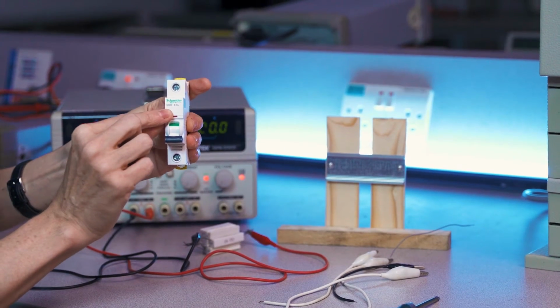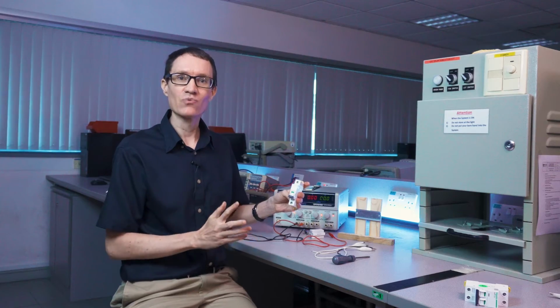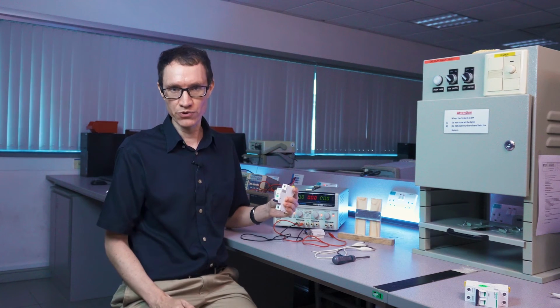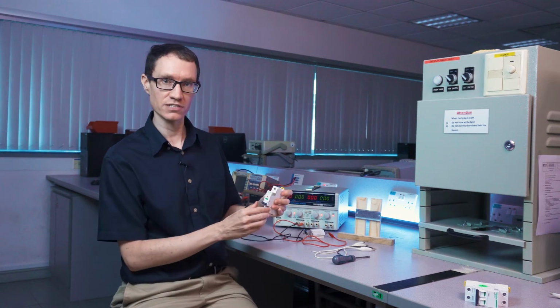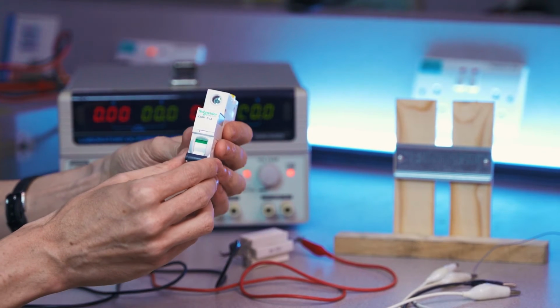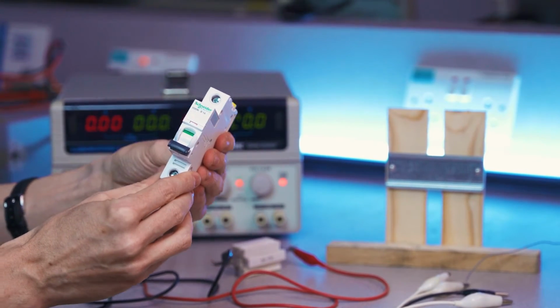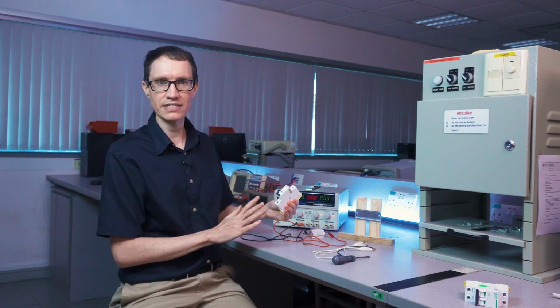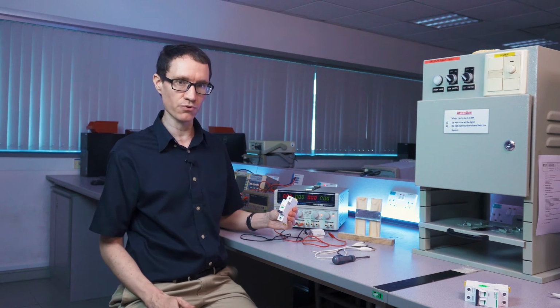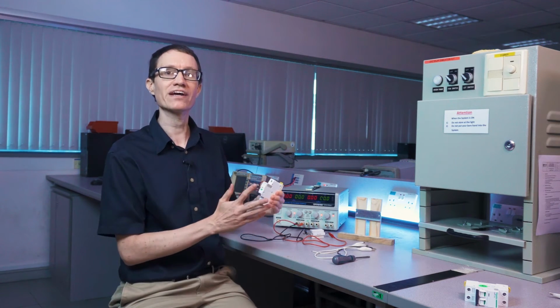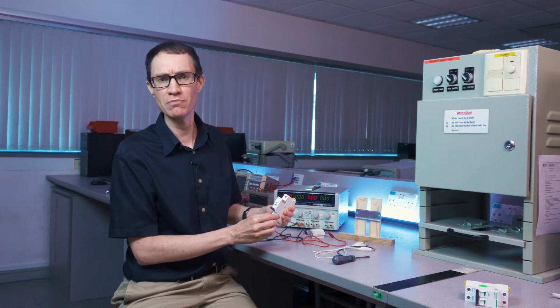This circuit breaker is only rated 1 ampere. That's a rather low rating compared to what you would normally find in a breaker box, for example, in a house. We're not going to be testing this circuit breaker at 230 volts. We're going to instead test it at a rather low voltage, and we're going to use the DC power supply. The tripping curve for DC currents will be a little bit different than the tripping curve for AC currents, but what we care about here is to just get the general shape of the curve.